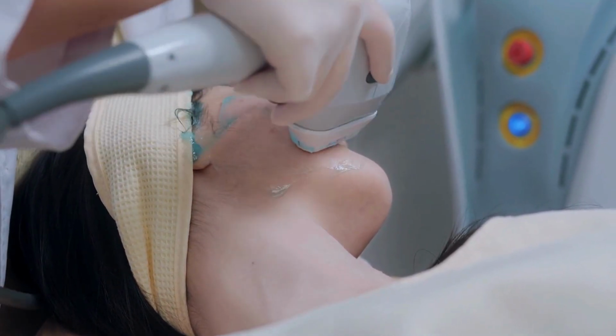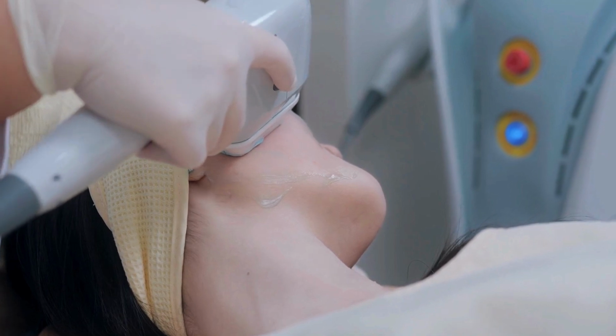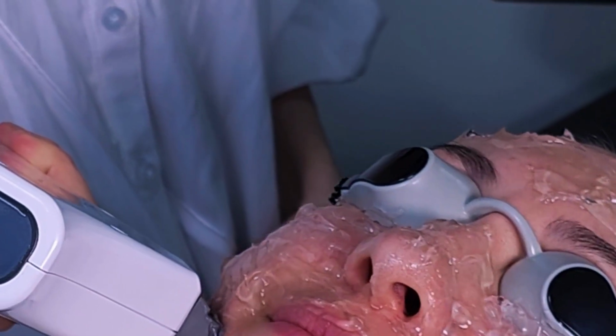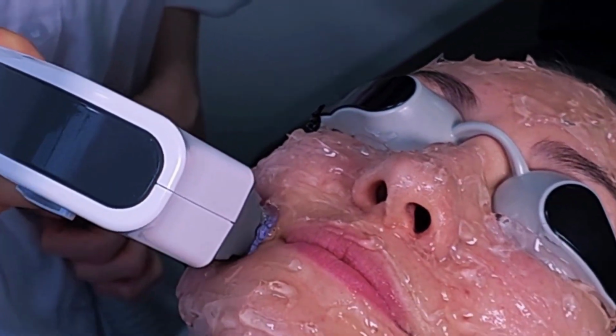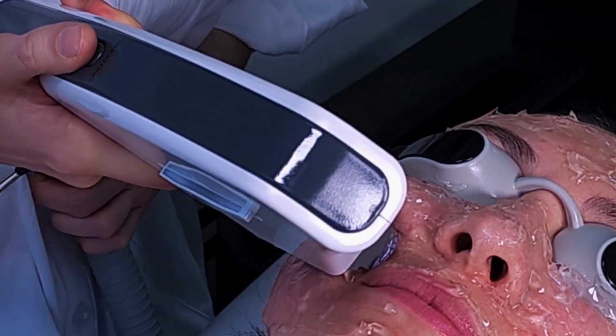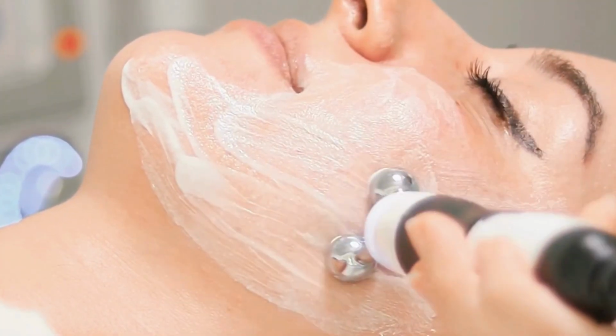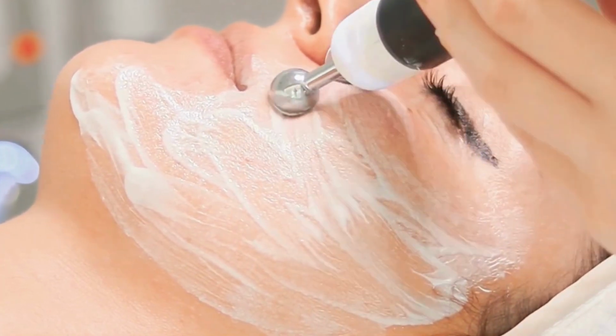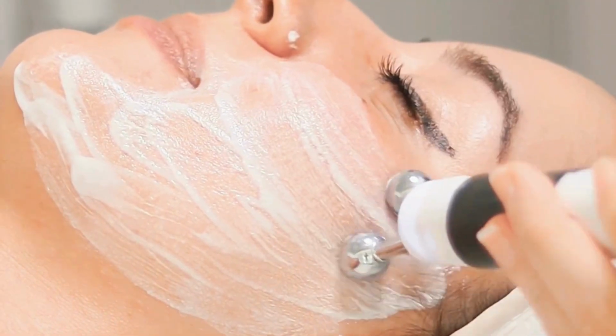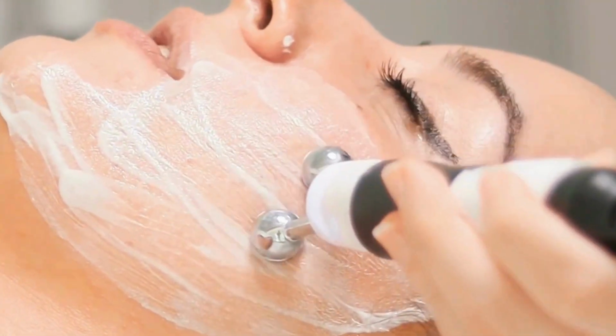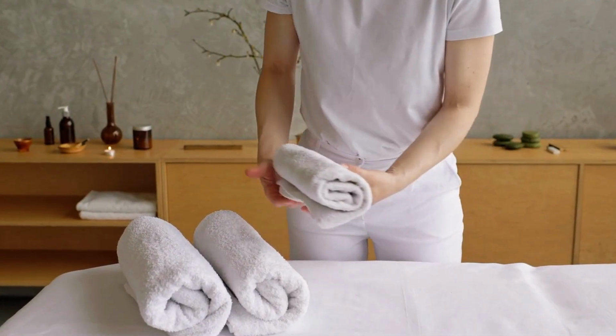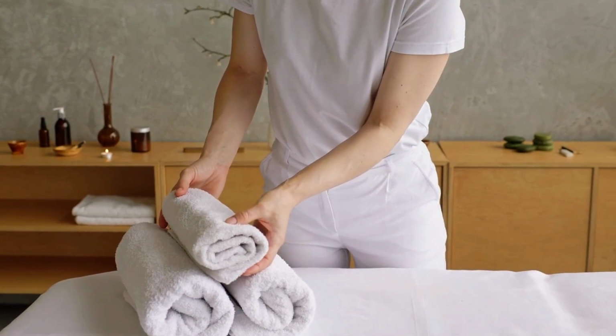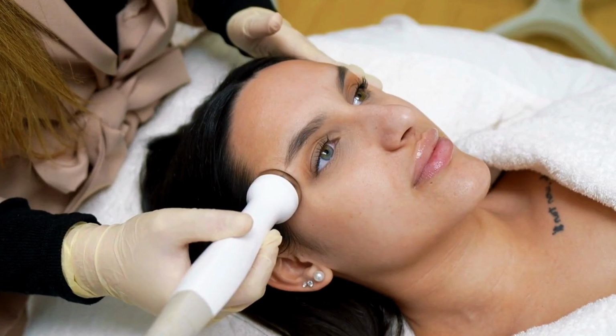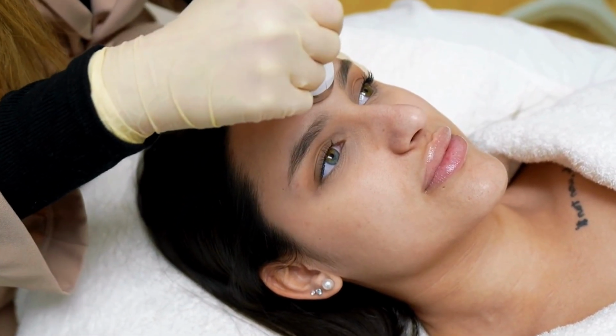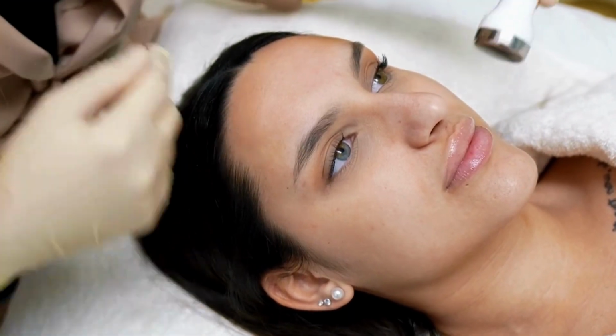When the energy converges at that focal point, it generates localized heat, around 65 to 70 degrees Celsius in a fraction of a second. This heat triggers what's called controlled thermal coagulation. Existing collagen fibers contract immediately, producing the visible tightening effect patients notice right after the procedure. But the result that actually matters happens over time. That controlled thermal injury activates the body's repair cascade. Fibroblasts, the cells responsible for collagen synthesis, are recruited to the area. Over 90 to 180 days, they produce new type 1 collagen, denser, more organized, and structurally firmer. This is exactly why HIFU doesn't deliver its full result immediately. The real lifting happens gradually, over 3 to 6 months.